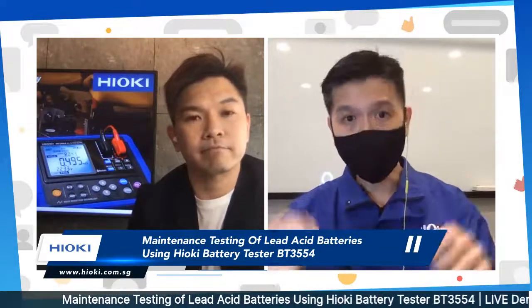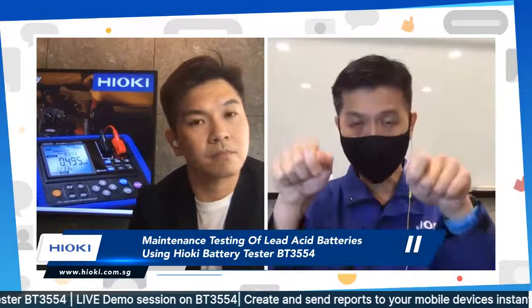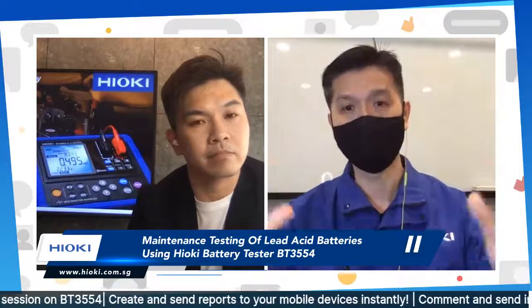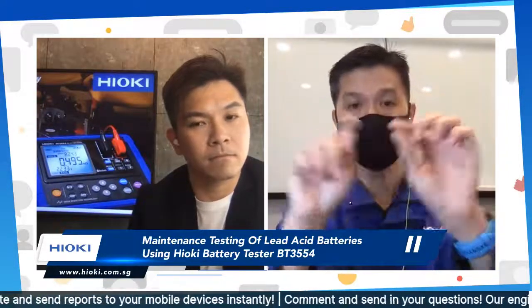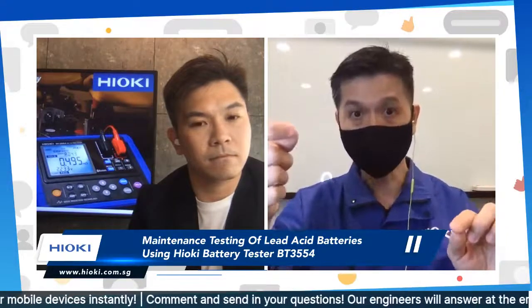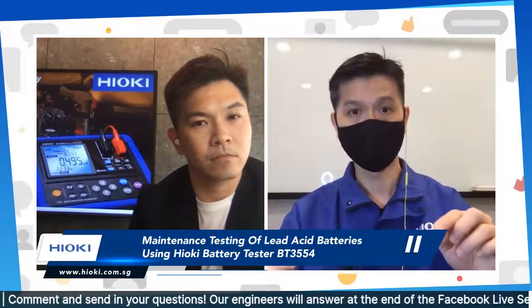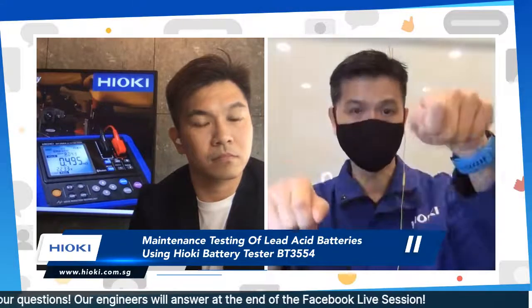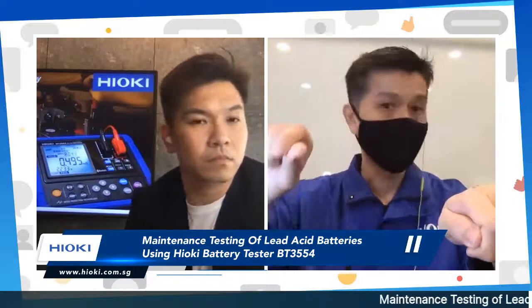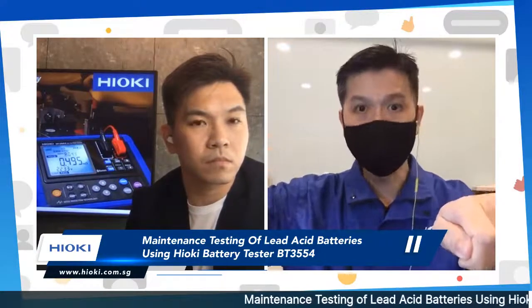Another thing customers like to ask is why does the fuse always blow so easily whenever doing measurement. The main reason is when you measure on a battery bank, there's usually a metal enclosure, and this metal enclosure is usually grounded to earth. Sometimes when customers are measuring, they touch the positive terminal, then get distracted and look at something else, and the other probe touches onto the metal enclosure.